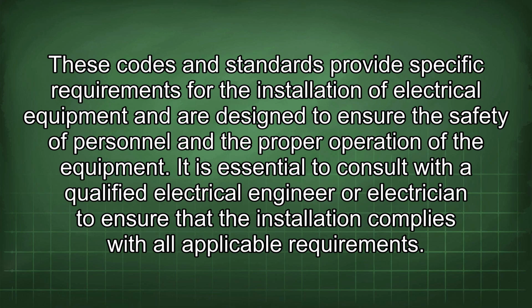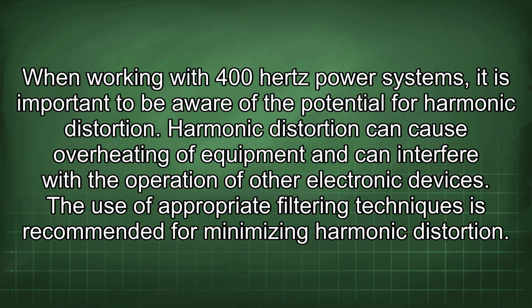These codes and standards provide specific requirements for the installation of electrical equipment and are designed to ensure the safety of personnel and the proper operation of the equipment. It is essential to consult with a qualified electrical engineer or electrician to ensure that the installation complies with all applicable requirements. When working with 400 Hz power systems, it is important to be aware of the potential for harmonic distortion. Harmonic distortion can cause overheating of equipment and can interfere with the operation of other electronic devices. The use of appropriate filtering techniques is recommended for minimizing harmonic distortion.